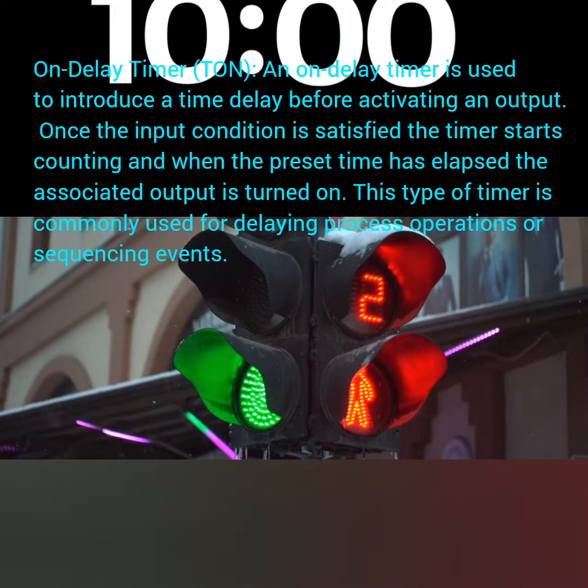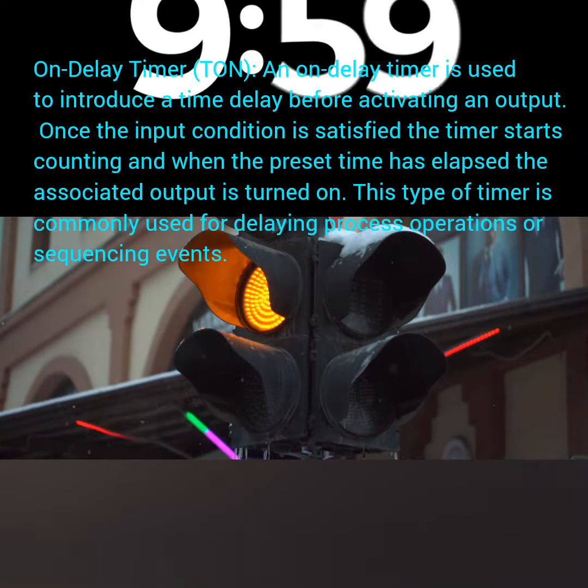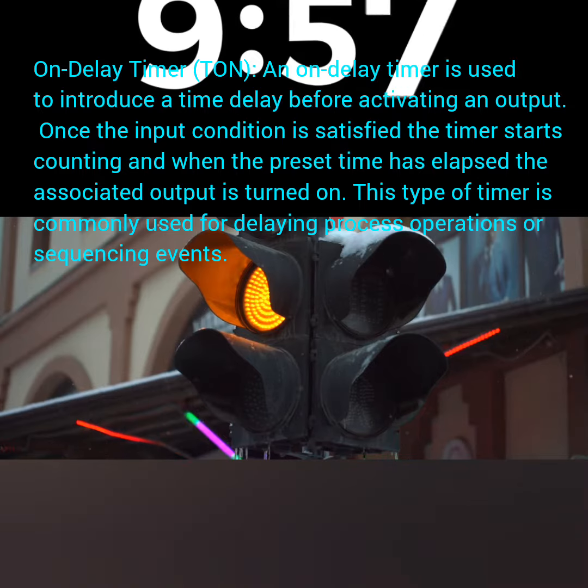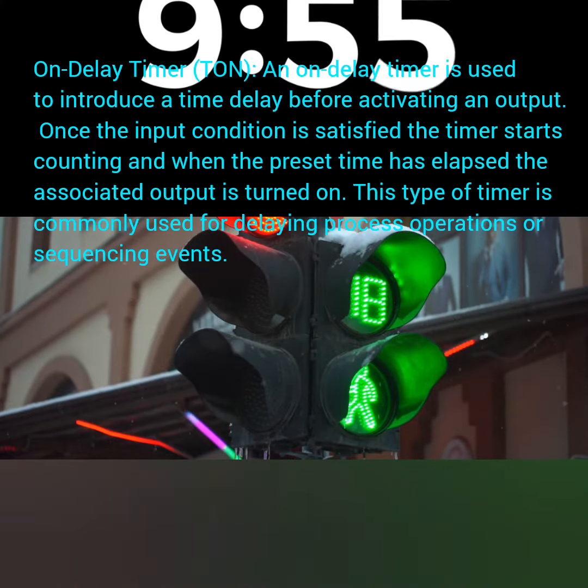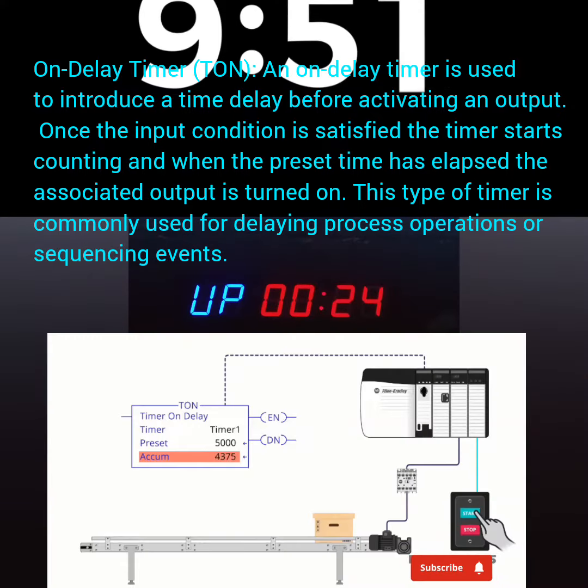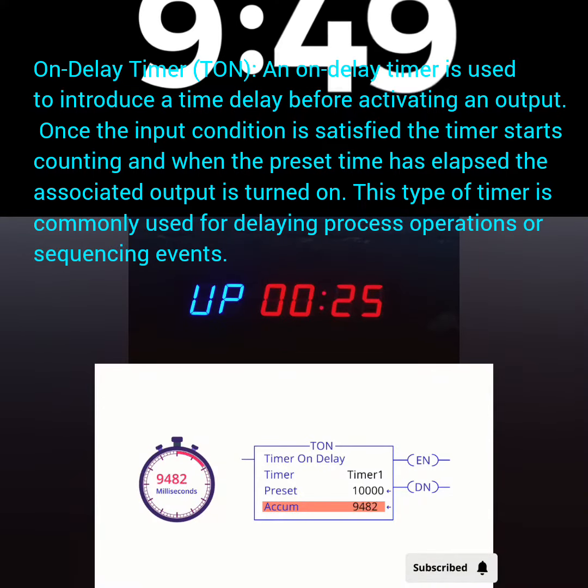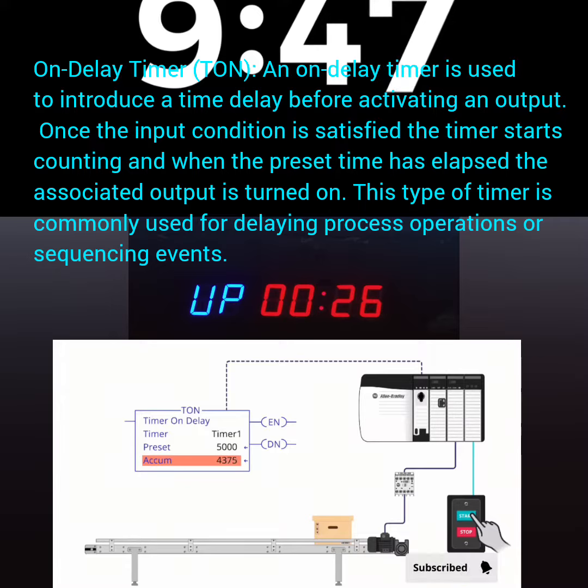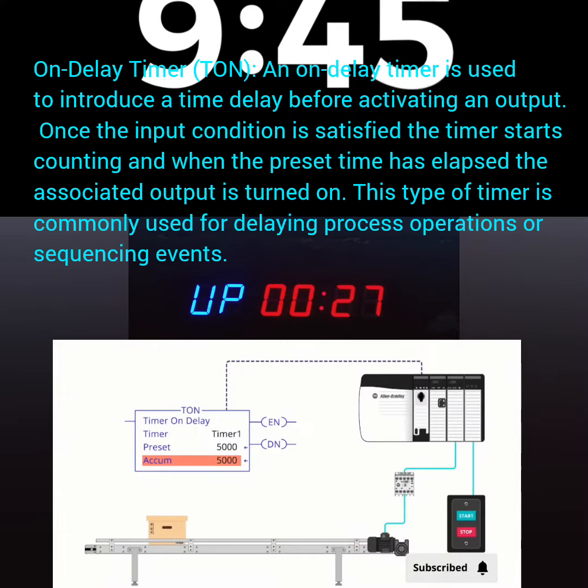1. On-delay timer, TON. An on-delay timer is used to introduce a time delay before activating an output. Once the input condition is satisfied, the timer starts counting, and when the preset time has elapsed, the associated output is turned on. This type of timer is commonly used for delaying process operations or sequencing events.